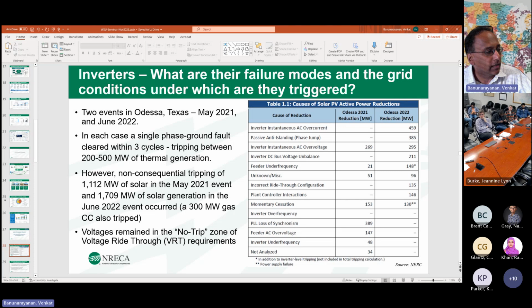The key here is the last one. Voltages remained in the no-trip zone of VRTs. The IEEE 1547 standard has LVRT, low voltage ride-through. The voltages did not go beyond that, which means the inverter should not have tripped. That's the bottom line, but they did, and these are the reasons.